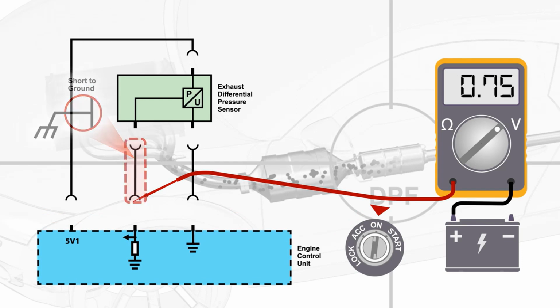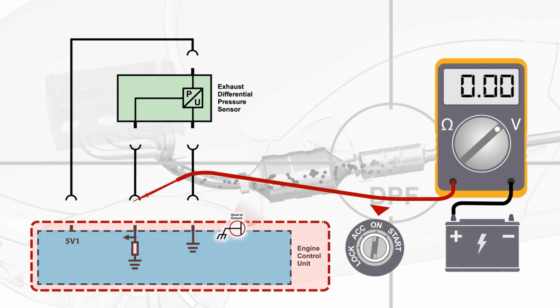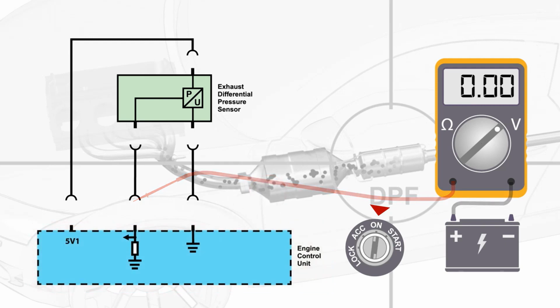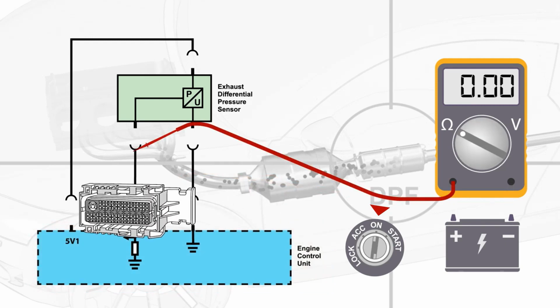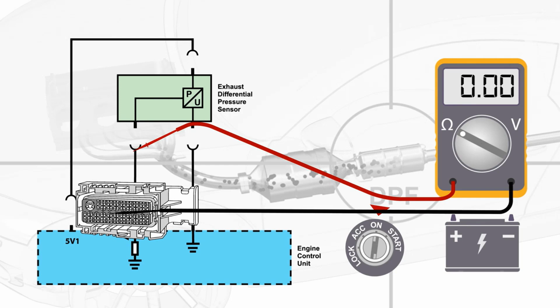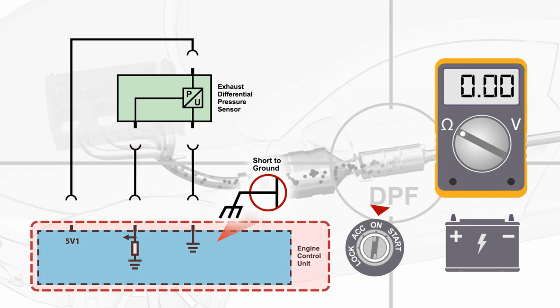If the meter displays 0 volts, then the short is in the ECM or a circuit from the ECM. To isolate between the two, perform a continuity test between the signal terminal and all other terminals in the ECM connector. If this test proved okay, then the short is in the ECM.